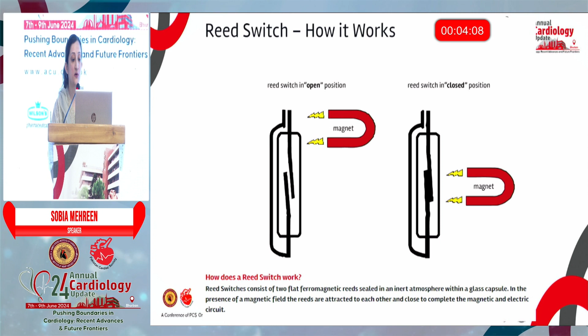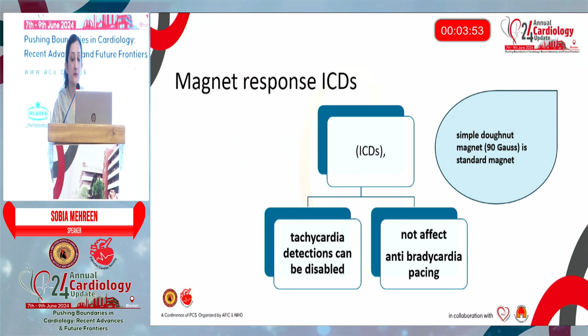The magnet response in ICDs causes the tachy detection to be disabled. So no tachy treatment like ATP or ICD shocks will be delivered. However, it does not affect the anti-Brady pacing in case of ICDs. The pacing mode will not be changed in ICDs.